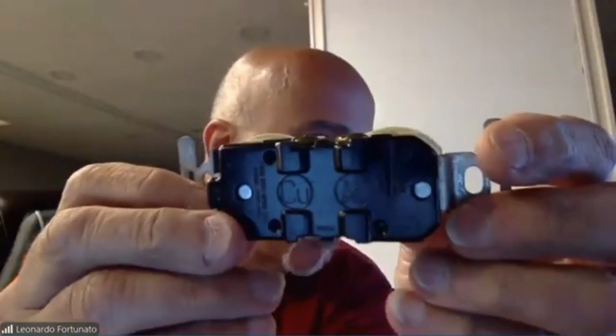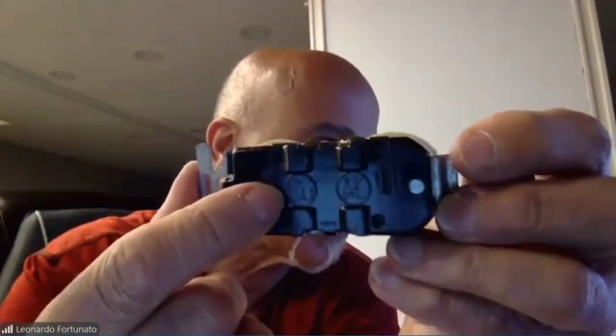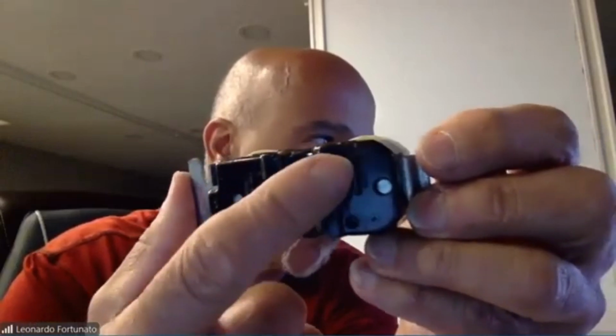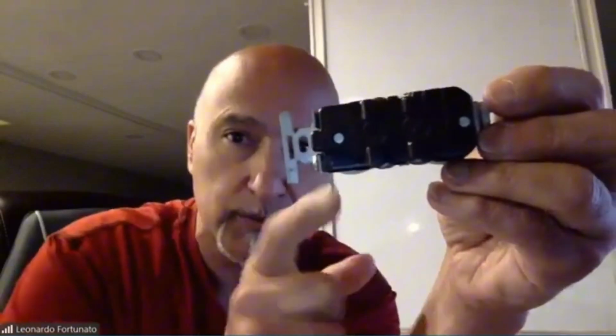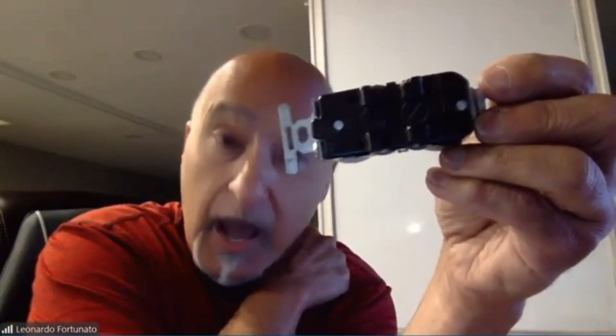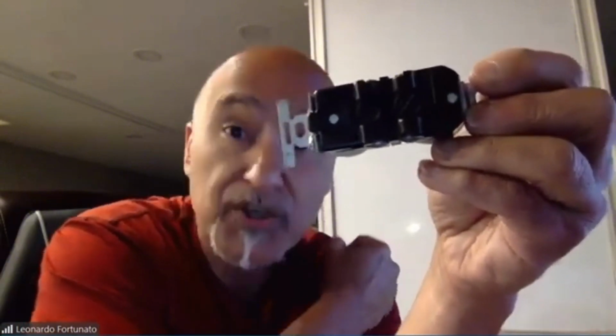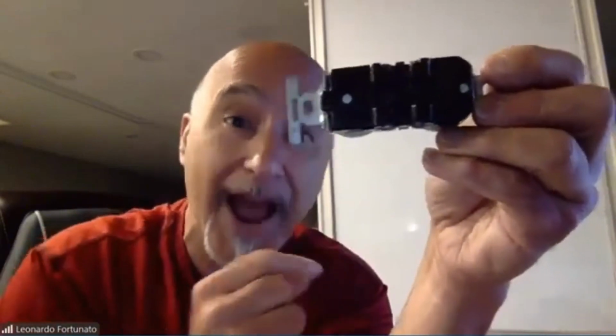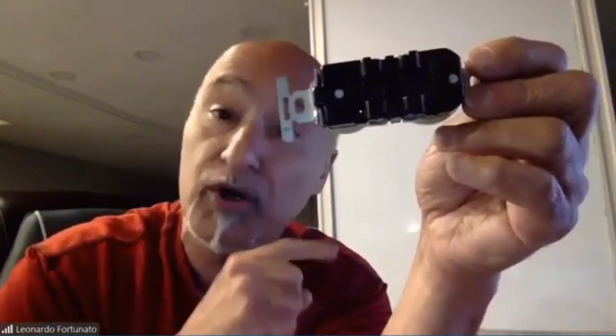Also, when we are looking at our receptacles, very important, you can see over here in a circle it says CU, and in this circle it says AL with a line through it. That's telling us this receptacle is good only for copper wire. Do not use aluminum wiring with this receptacle. Of course, when using aluminum wiring, we wouldn't want to use this receptacle - we would have to get a receptacle that said not good for copper, good for aluminum. So we'll also see those markings on our receptacles.